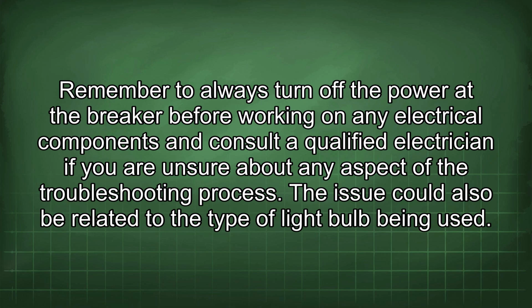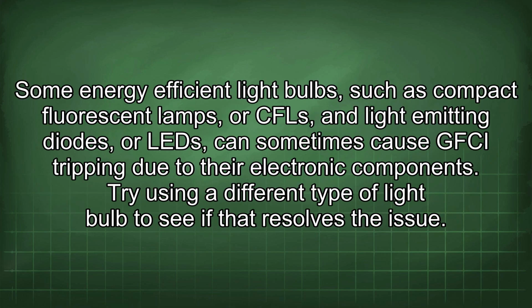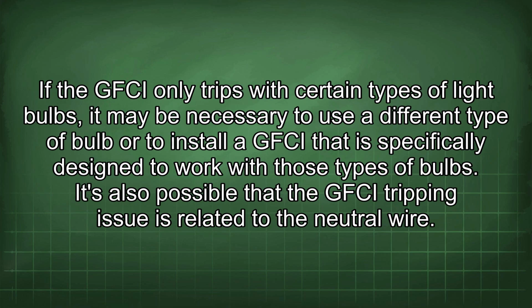The issue could also be related to the type of light bulb being used. Some energy-efficient light bulbs, such as compact fluorescent lamps, or CFLs, and light-emitting diodes, or LEDs, can sometimes cause GFCI tripping due to their electronic components. Try using a different type of light bulb to see if that resolves the issue. If the GFCI only trips with certain types of light bulbs, it may be necessary to use a different type of bulb or to install a GFCI that is specifically designed to work with those types of bulbs.